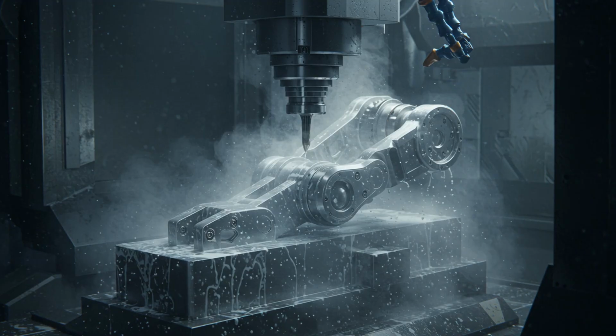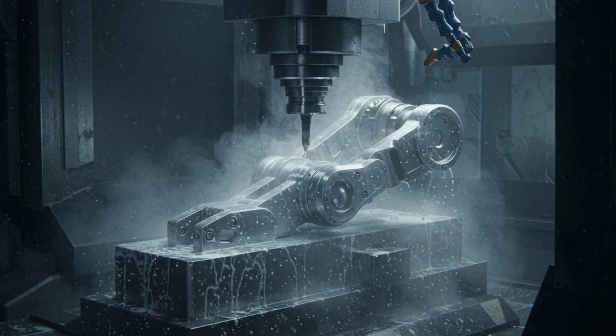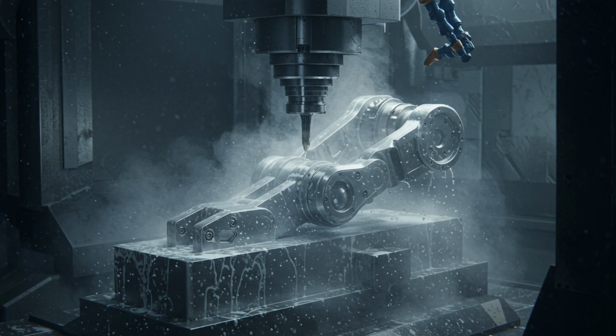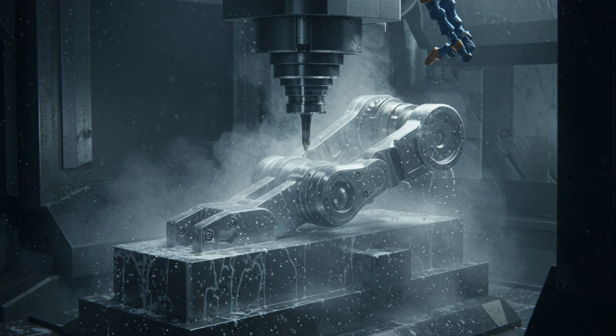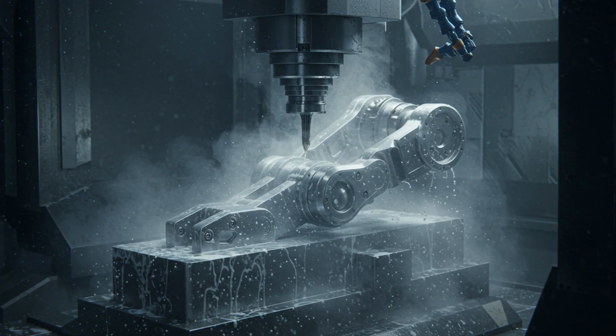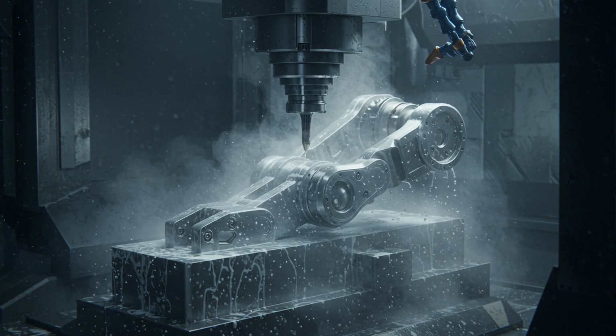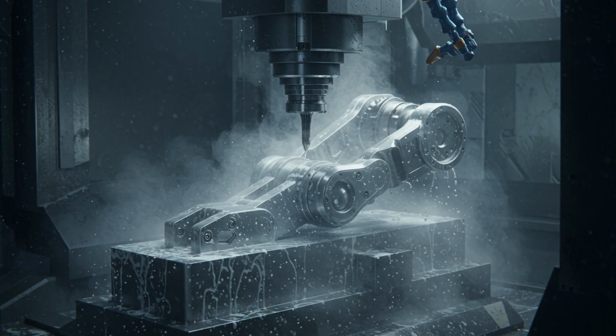The journey begins with the chassis and the mechanical limbs. These aren't built from ordinary steel. Engineers utilize aerospace-grade aluminum and high-modulus carbon fiber to ensure the robot is incredibly light, yet exceptionally rigid. Why? Because even the slightest flex in the metal under pressure could result in a catastrophic error deep inside a patient's body. Each arm segment is precision machined using 5-axis CNC mills to tolerances of less than 10,000ths of an inch.